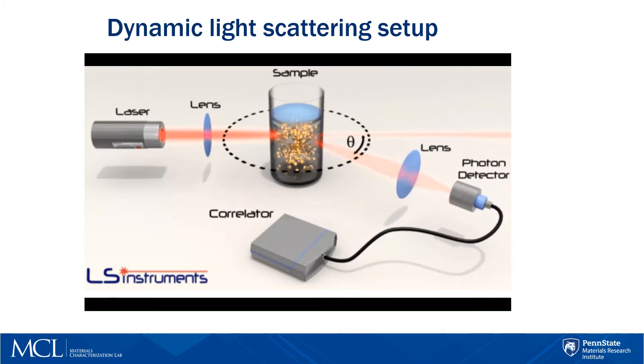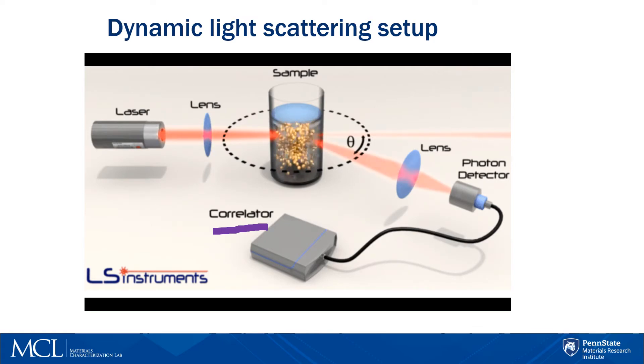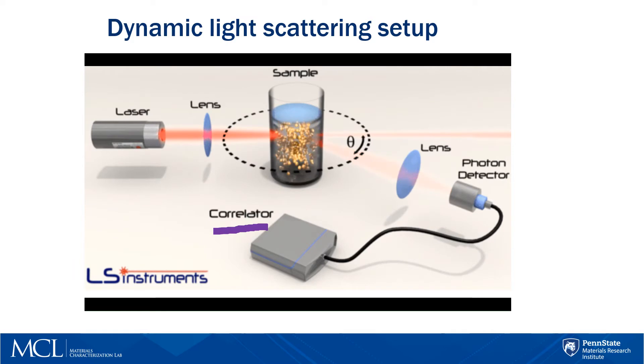Another important part of the system is the correlator. The correlator takes very rapid snapshots of the scattering light on the nanosecond and microsecond scale, one after another. These changes in light intensity with time allow computing a correlation function, which we then analyze to get the diffusion coefficient of the particles.